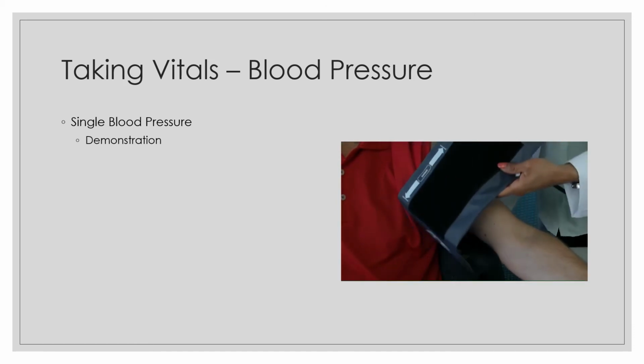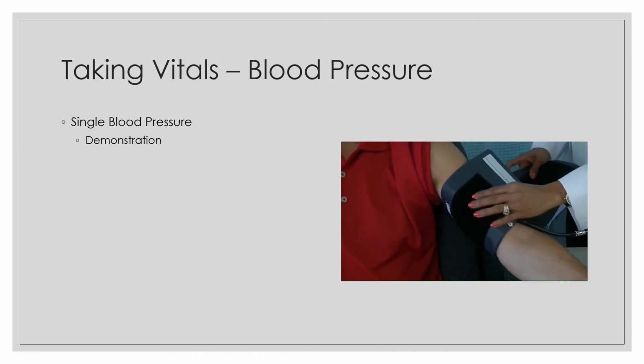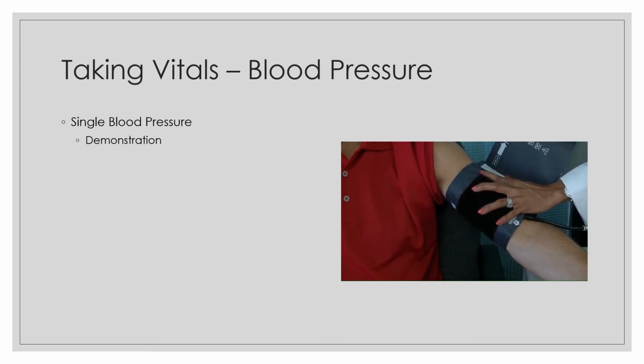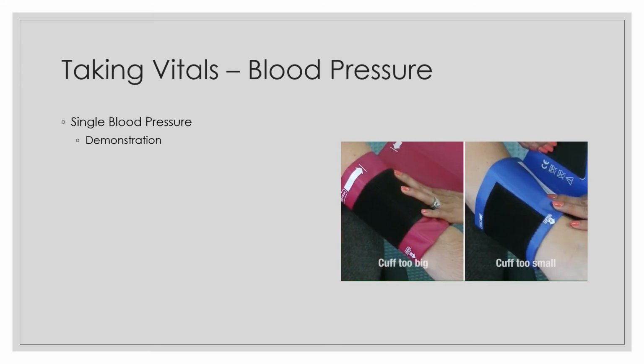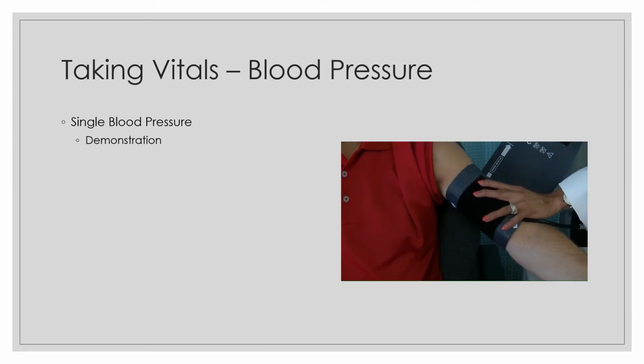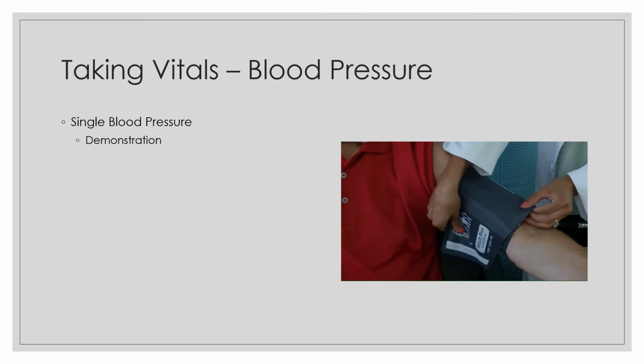When ready, place the cuff around the arm. The cuff index line should fall within the printed range markers. If not, select a larger or smaller cuff to ensure an accurate reading. Make sure the arm is relaxed and supported, and ask the patient to stay still and quiet.